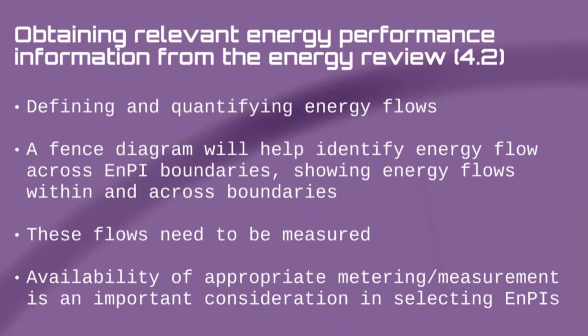Wasn't listed, or isn't listed in the standard, as an example energy performance indicator, but the importance of appropriate metering to formulate your energy performance indicators does mean that there's a good case for making the availability of metering an energy performance indicator in the early life of a system. In other words, to what degree, what percentage of your energy use can be identified through submetering.